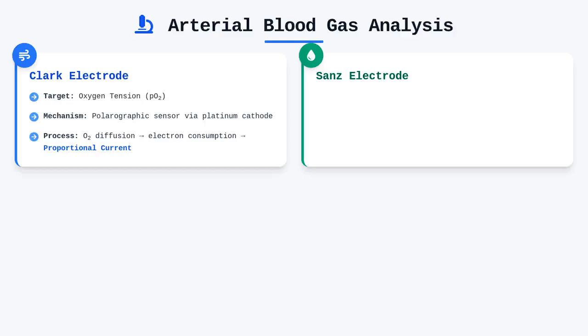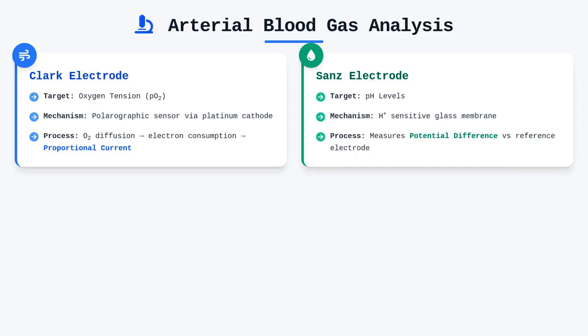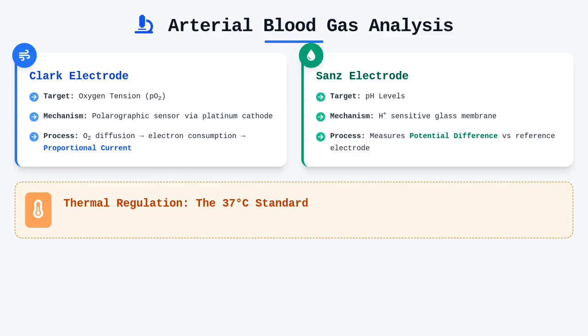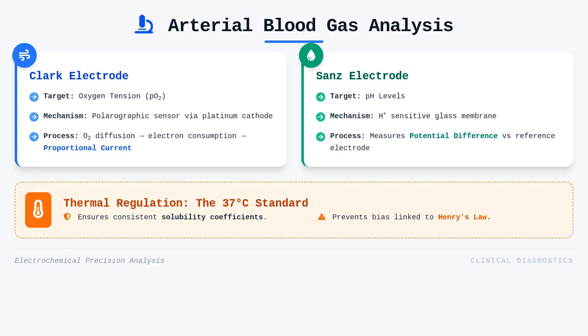Conversely, the Sanz electrode measures pH by monitoring the potential difference across a hydrogen ion-sensitive glass membrane compared to a reference electrode. Because these chemical reactions are exquisitely temperature-sensitive, the cuvette must be strictly regulated at 37 degrees Celsius to ensure that solubility coefficients remain consistent during measurement. Failure to maintain this thermal stability introduces significant bias, as the partial pressure of gases in solution shifts predictably with temperature fluctuations according to Henry's law.